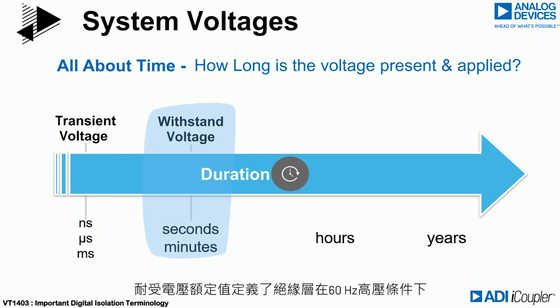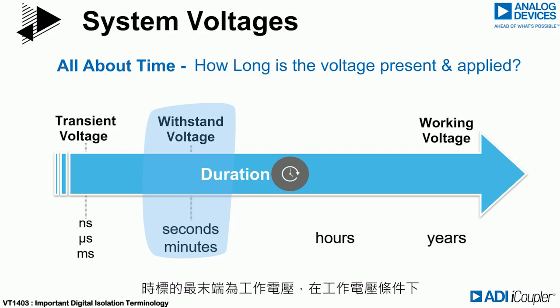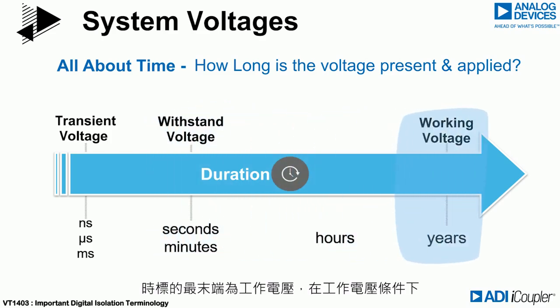The withstand voltage rating defines the ability of the insulation to survive at least one minute with a 60 Hz high voltage sinusoid. At the extreme end of the timescale is the working voltage, in which the insulation must survive continuously for decades.